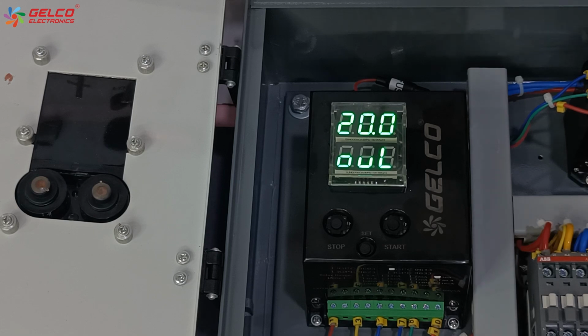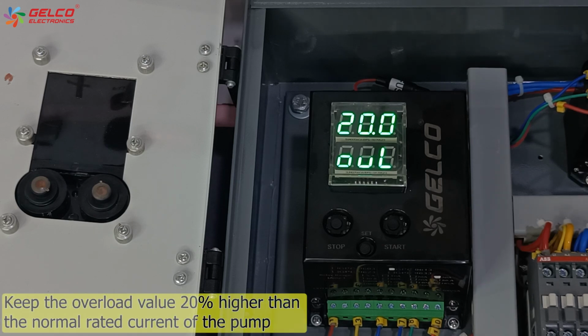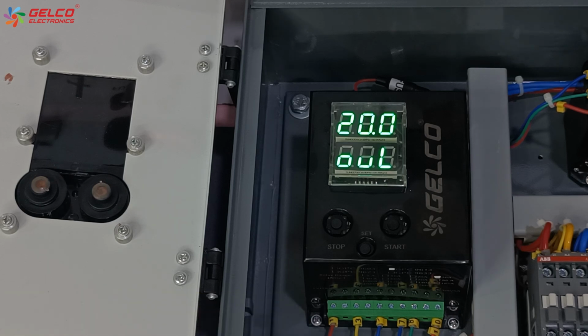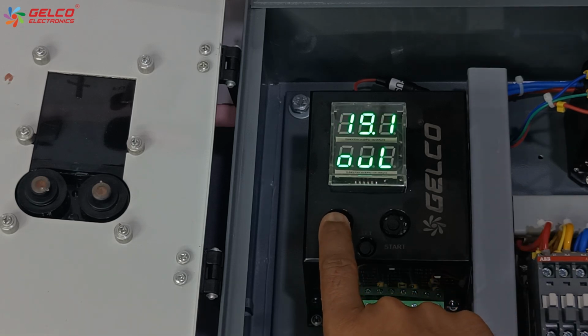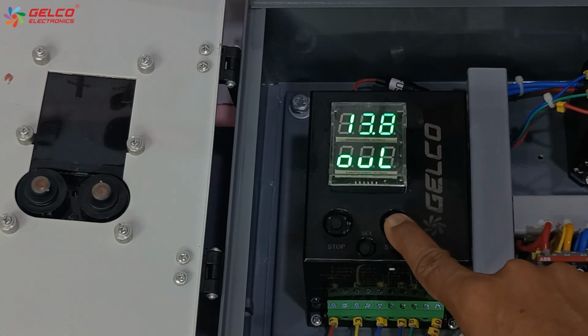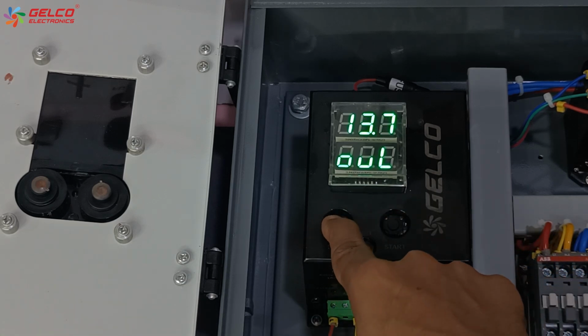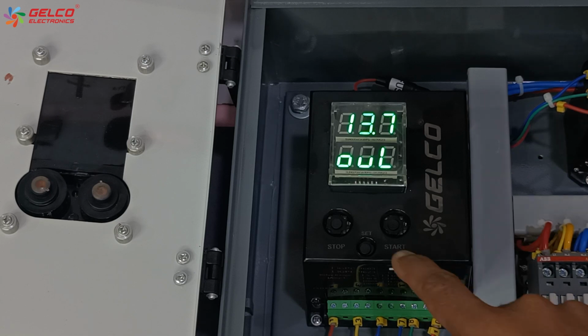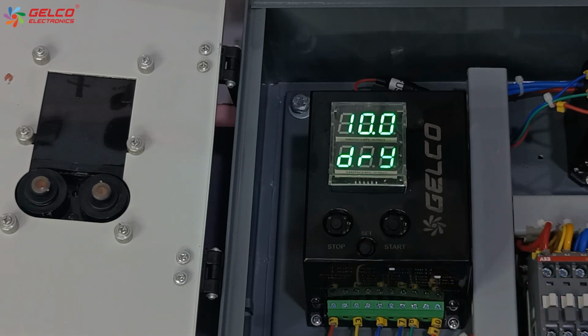Overload option will appear on the panel's display. You have to keep overload value 20% higher than the normal rated current of the pump. The normal rated current of our pump is 11.4 amperes, so 20% of that will be 13.7 ampere. So we will set the overload value to 13.7 ampere. Press the set button after the value is set.